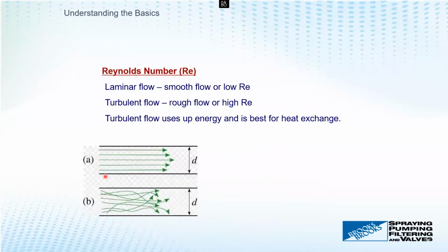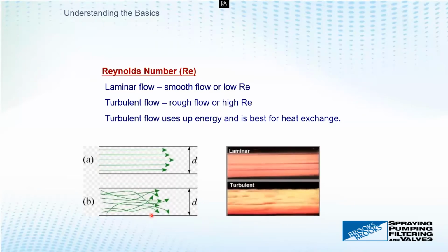So that rough or turbulent pressure drop is all based on the Reynolds number, for those of you that are familiar with it. So laminar flow, as we talked about, is really good in piping. It's nice and steady. Everybody stays in their lanes and it flows really easy with the least amount of energy. Turbulent flow, however, in a pipe is not very good. It uses lots of energy, pretty messy, causes erosion, all sorts of things. But in a heat exchanger, it's what offers up the energy into the sides of the pipe, or in our case, to the walls of the plates. And that gives us the energy transfer and more efficient heat transfer.